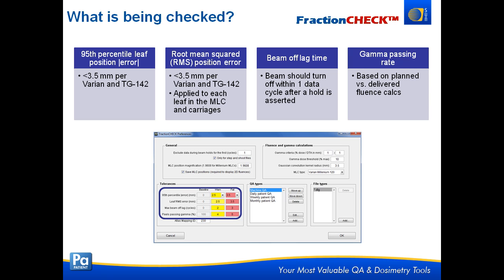These first items are all machine performance related — positioning errors of MLCs — and they're very good for machine QA, but they don't necessarily tell us what happened to our patient. Just knowing we have a 2 mm error in an MLC leaf isn't enough. What we do behind the scenes is calculate full fluences and a passing rate of planned versus delivered fluence calculations, translating all of these machine errors to say: what did that actually do to my patient's delivery?